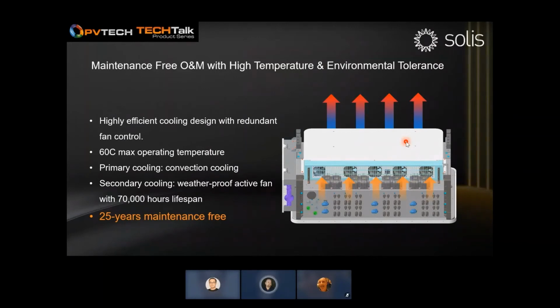But Gary, sorry for interrupting. Yes, Pedro. If my maths are correct, 70,000 hours makes not 25 years, maybe 5. So is the number wrong? Yeah, no, the number is right, but look at it this way. You're probably calculating the 70,000 hours at 24 hours a day. But if we look at the PV inverter, the inverter operates at peak 8 to 9 hours, but taking into account the effective solar radiation and that our fan is activated by temperature, the fan in this unit will only operate probably 4 to 5 hours a day. And if you divide that 70,000 hours by 4 or 5, that actually gives you quite some time to play around with. So this is how we guarantee 25 years of maintenance-free solutions to you.